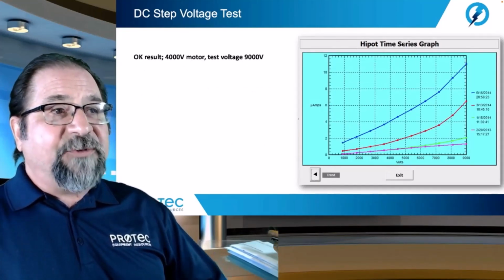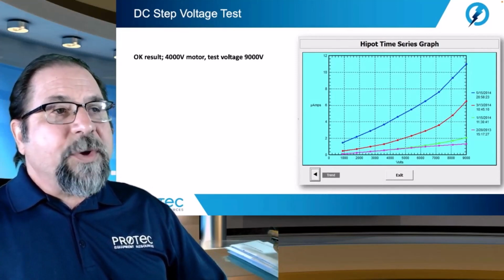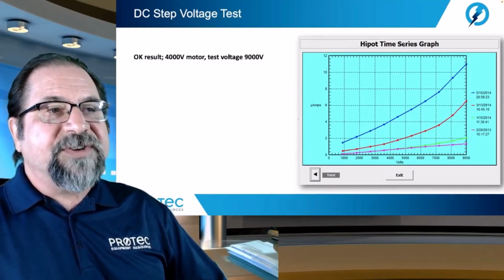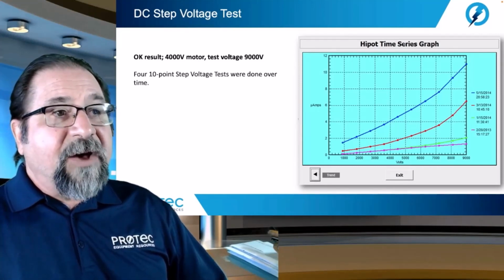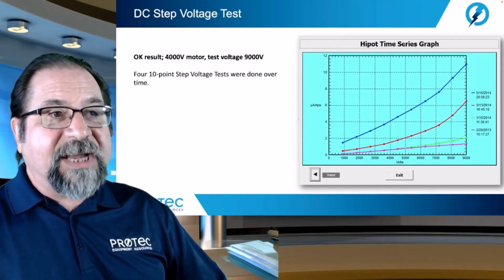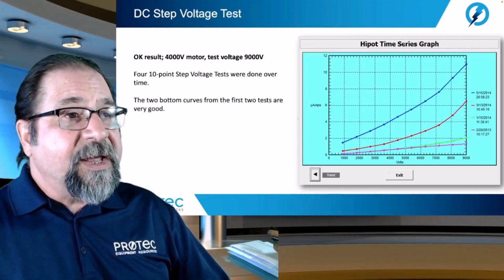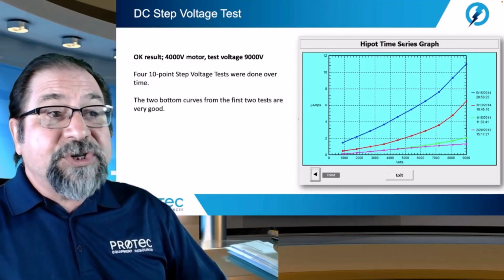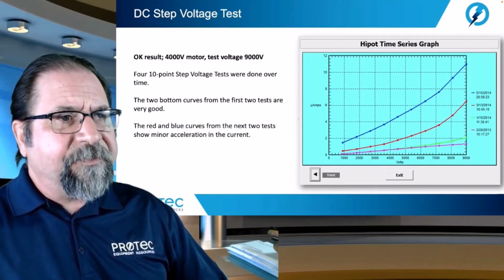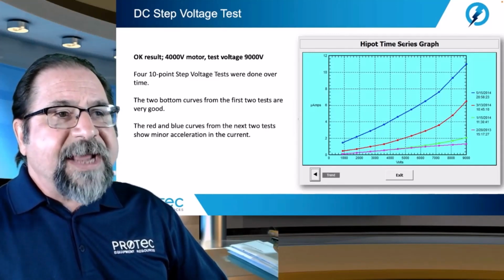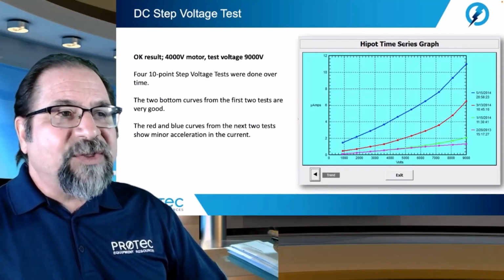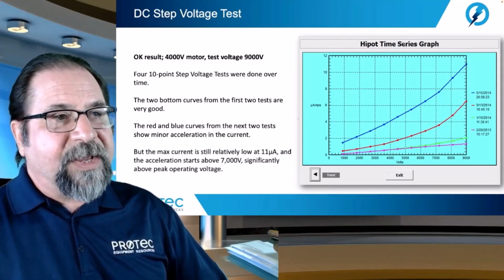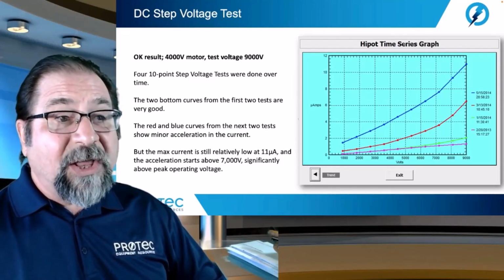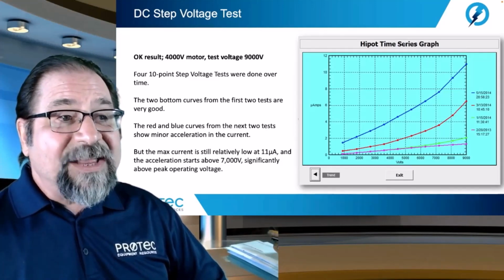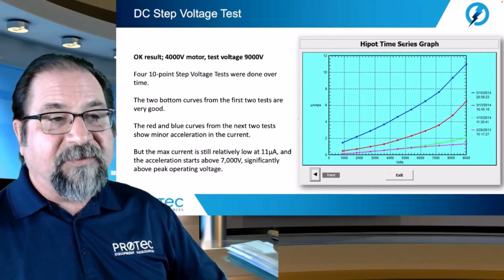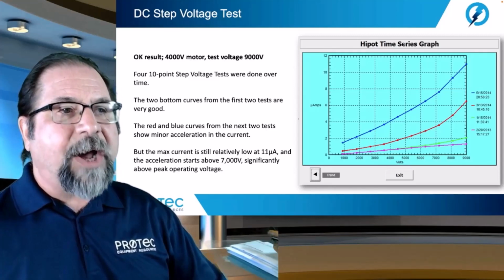Now here's a test result for an okay result. Here a 4,000 volt motor was tested using a voltage of 9,000 volts. Four 10-point step voltage tests were done over time. The two bottom curves from the first two tests are very good. The red and blue curves from the next two tests show minor acceleration in the current. But the maximum current is still relatively low at 11 microamps, and the acceleration starts above 7,000 volts, significantly above peak operating voltage.